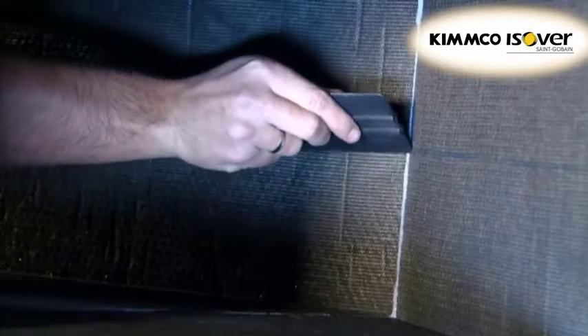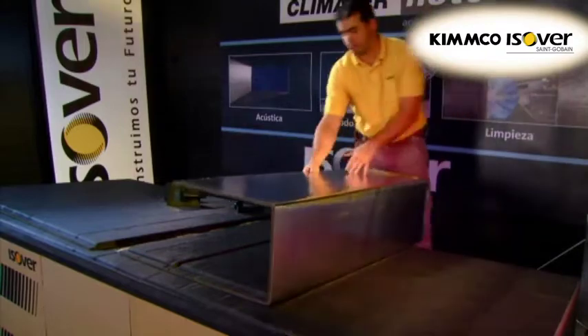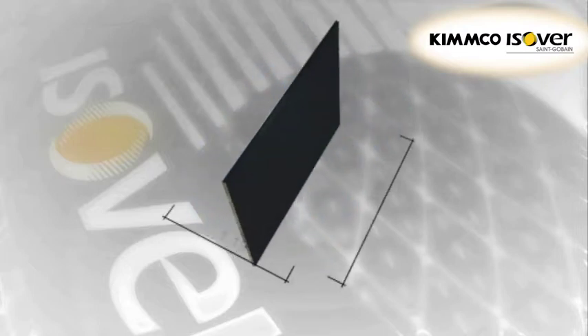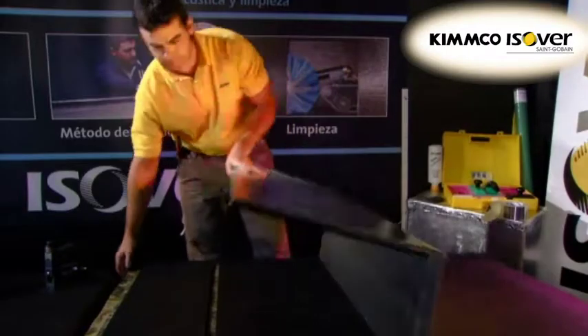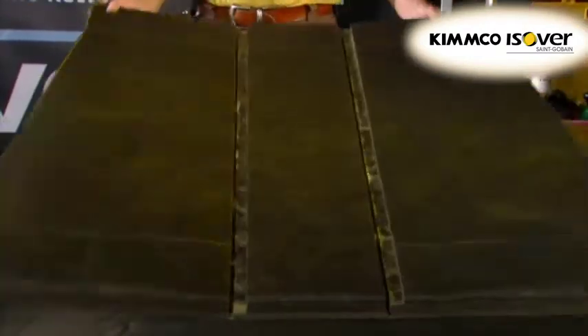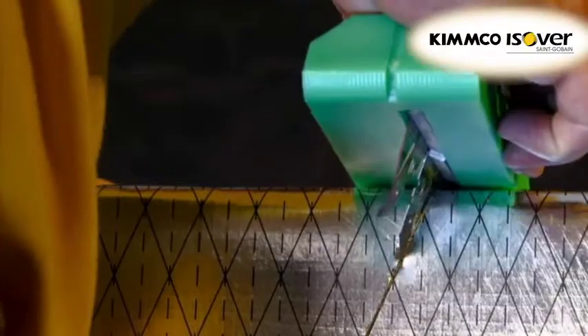Climaver are high-density glass-wool duct boards used for the installation of self-supporting air ducts. Climaver boards are rigid glass-wool boards which are 3 metres long and 1.19 metres wide and have a thickness of 25 millimetres. The boards are lined on both sides, with a reinforced aluminium foil on the outside of the duct and glass tissue, aluminium or glass fabric on the airstream side.